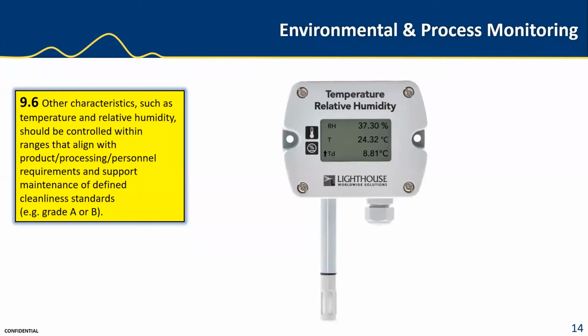If you look at 9.6, other characteristics such as temperature and relative humidity should be controlled within ranges that align with product processing, personnel requirements, and support maintenance of defined cleanliness standards, e.g. grade A and B. I would also strongly recommend that your facility has a continuous environmental monitoring system with temperature, relative humidity, and also differential pressure sensors, which are independent of the building management system. The BMS sensors are for control, and the EMS sensors are for the validated data. EMS systems are validated according to cGMP standards and GAMP.